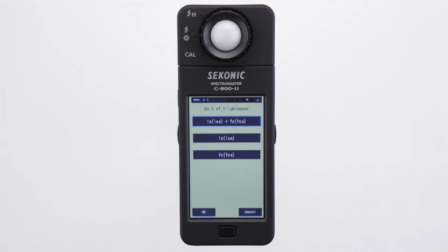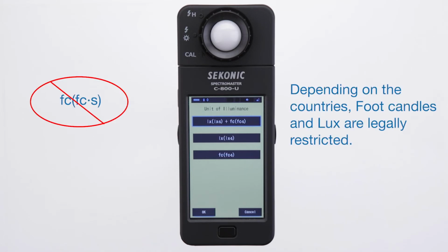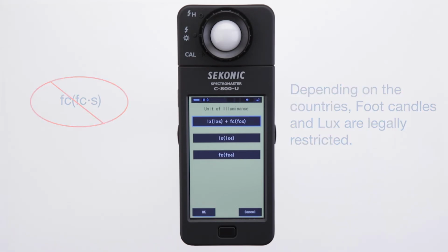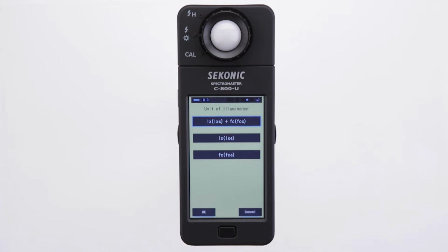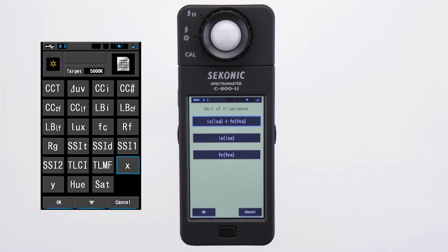In some countries, the C-800 doesn't display illuminance and exposure in foot candles and foot candle seconds due to legal restrictions. In this case, the unit of illuminance button will not appear in the setting screen. While you're in the measuring screen, you can select both lux only or foot candle only. This setting is located in the display item selection screen.